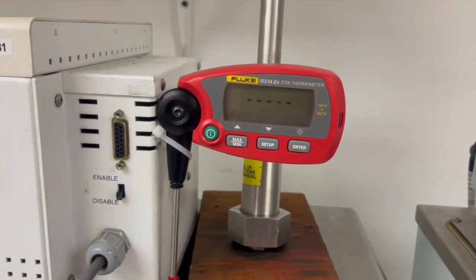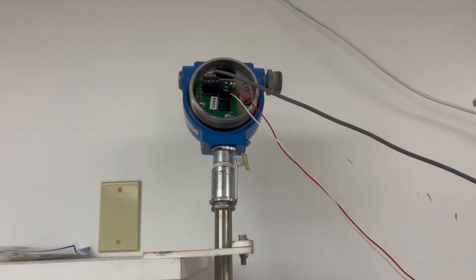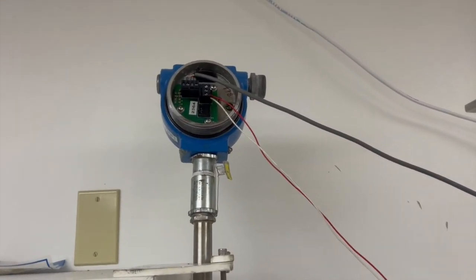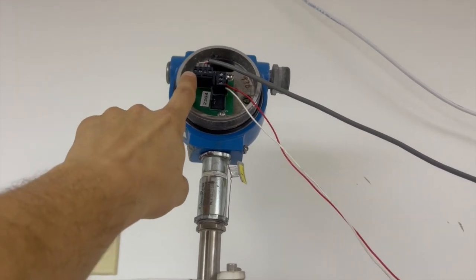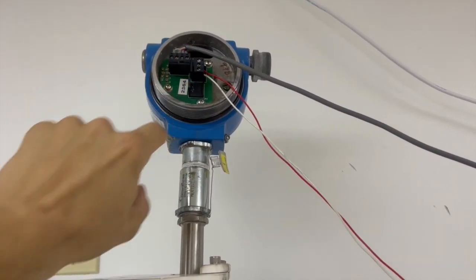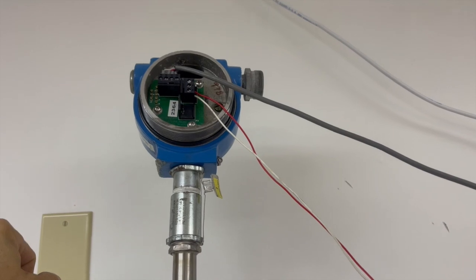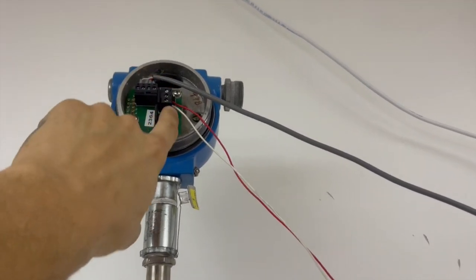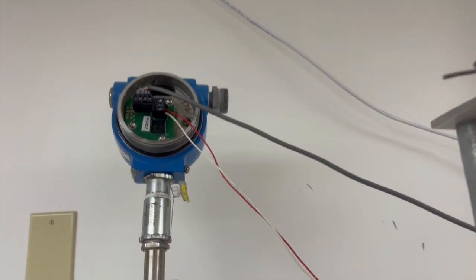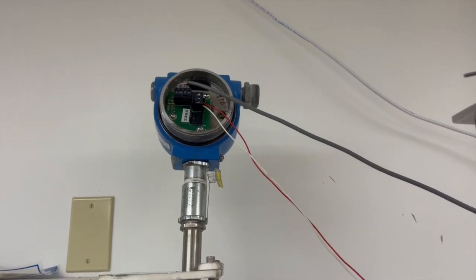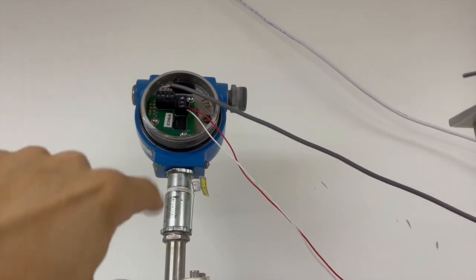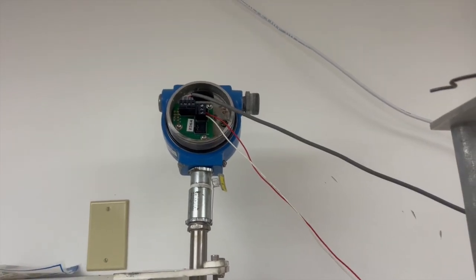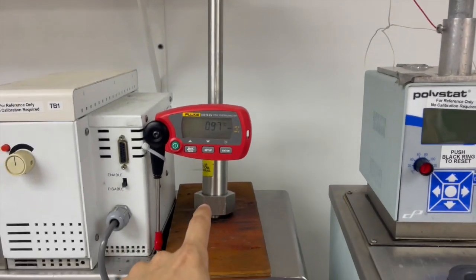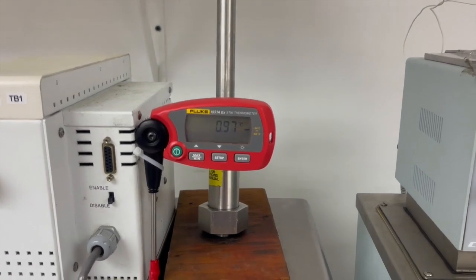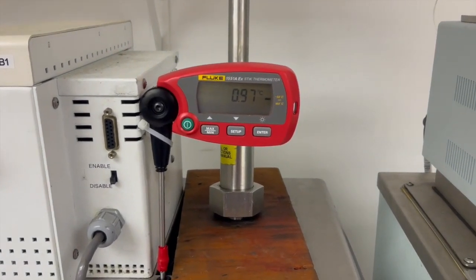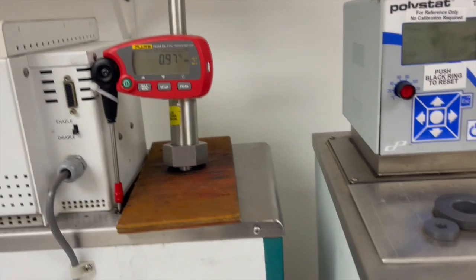So now that we have the JF-1A in the temperature bath, we have it hooked up to power. I have power running through the serial port. You won't. You're going to need to hook up both the conductivity and the temperature to power the sensor. However, you need the temperature loop powered up for sure. You'll get 2 power supplies with this kit, so just power both loops. They need to be running on separate loops, however. You can see we have it running. We have the temperature being measured here. It's 0.97 right now, and we need to let this soak for 30 minutes.